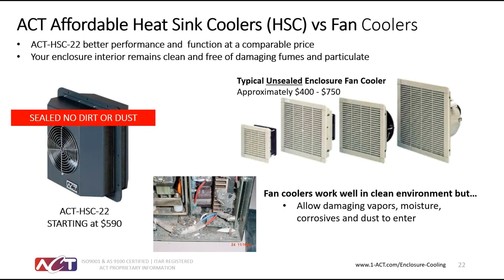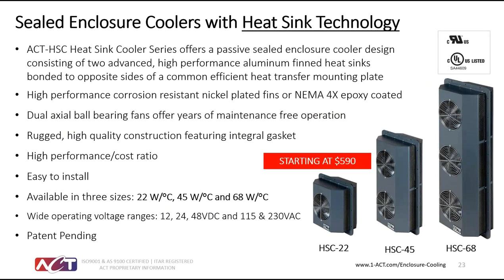So the heat sink coolers, they're pretty reasonable. They start at $590, and they compete pretty much with unsealed enclosure fan coolers. And a typical cabinet you'll see in the field, you'll find dust and dirt, and I'm sure over the years you've seen a number of cabinets that just weren't cared for, or they were left open, or a number of reasons. And so that's another good reason to use a sealed enclosure cooler.